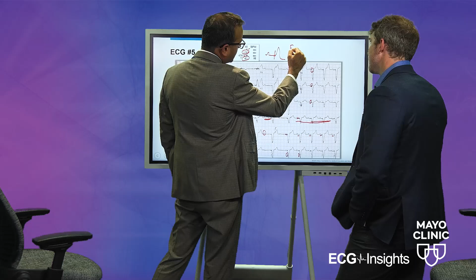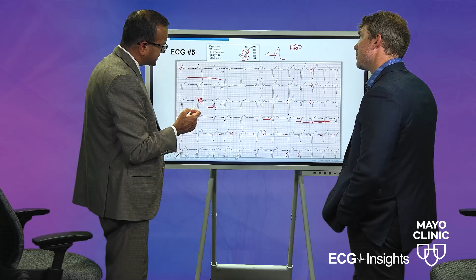But some novel devices, or leadless pacemakers where you don't have an actual atrial electrode, pick up atrial activity by several different methods, and that may work sometimes and may not work sometimes. So for example, it probably did not pick up this one, but you still got ventricular pacing. But here there was good AV synchrony. This can happen in patients with certain types of leadless pacemakers who don't pace in the atrium and don't have an electrode in the atrium to sense, but can figure out atrial activity due to several algorithms which are programmed in. This can also happen in pacemaker or ICD leads which have an atrial sensing electrode. If that atrial sensing electrode doesn't pick up the atrial activity, you will still see pacing if the patient is dependent on the pacemaker, but the PR interval can be variable as you have shown here.